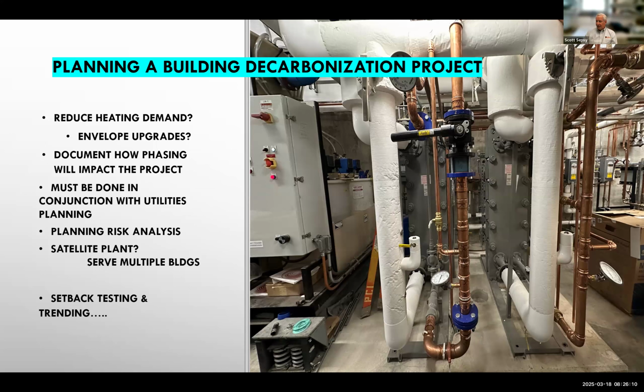Ideally, the district hot water system arrives at the building just in time. And if it doesn't, you stay on your parallel system. That's another thing about risk and phasing. Or you'd have to rent a hot water boiler, and we've had to do both. Understand as much as you can about the potential future plans of the building and optimize the path for new utilities into the building. Utilities planning also should include removing old steam and condensate piping systems and their parasitic losses.